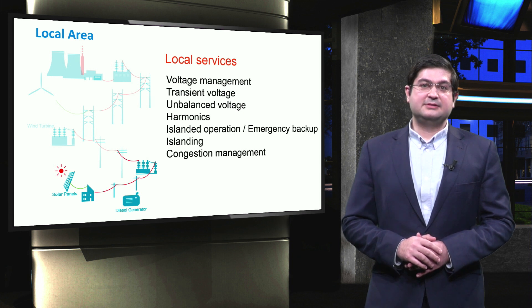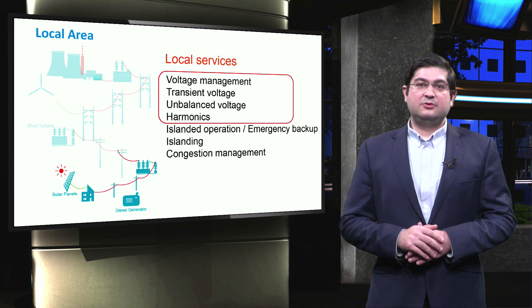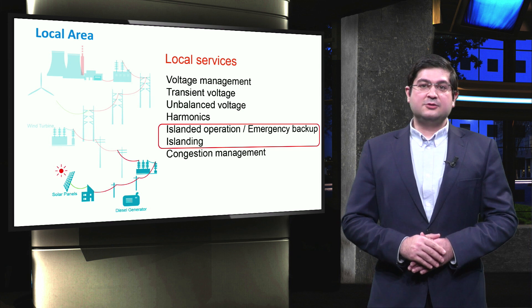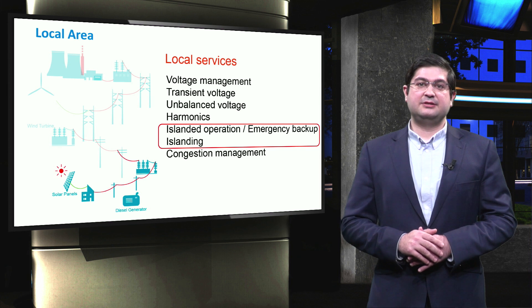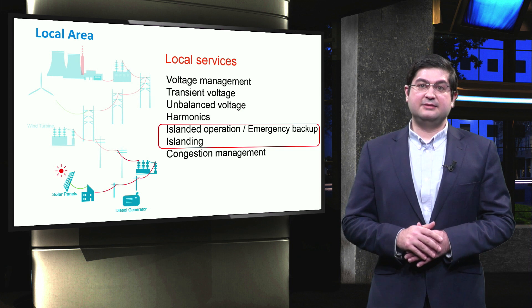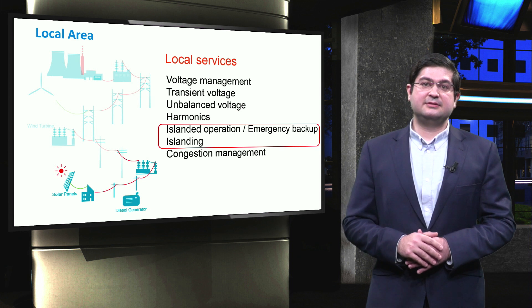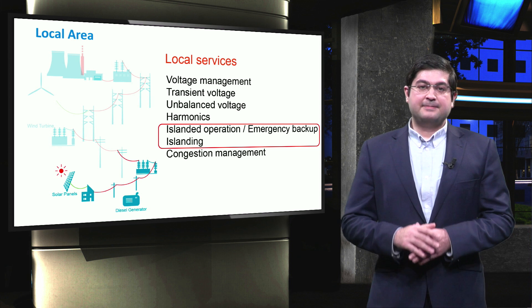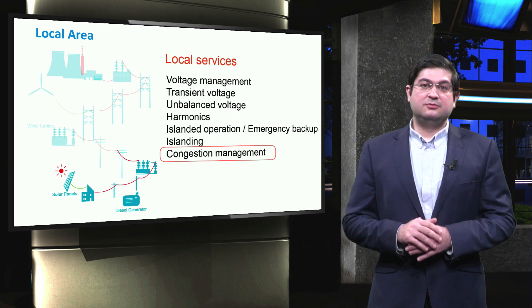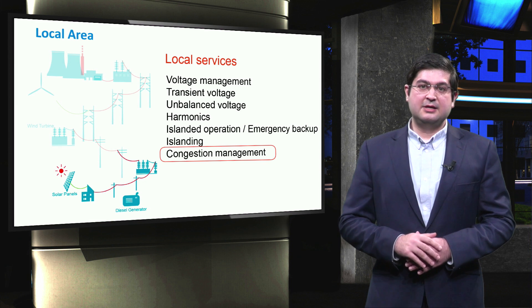At lower grid levels, ancillary services are generally considered as local. The voltage is an example of a local signal, and voltage phenomena include local voltage management, transient voltage, unbalanced voltage, and harmonics. Also, within the context of microgrids, islanded operation and emergency backup are provided for a small grid area. Moreover, a microgrid should be able to ensure safe transition from grid connected to islanded modes, and vice versa. The safe transfer from grid connected to islanded mode is called the islanding process. Another location-specific issue, which can occur at both transmission or distribution grid, is the congestion of the electrical lines.